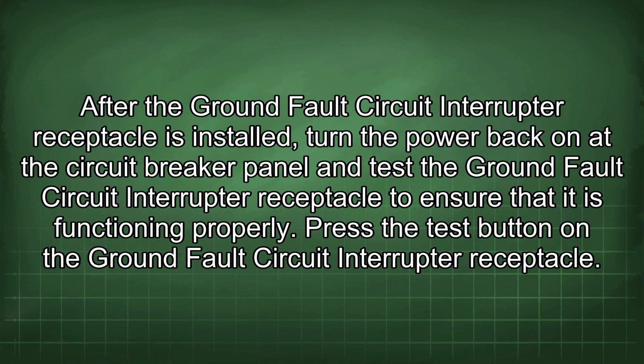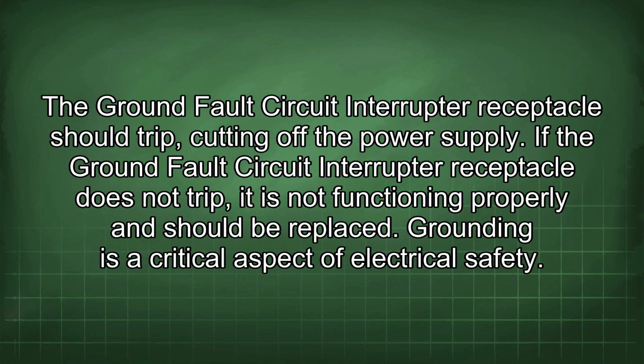Press the test button on the ground fault circuit interrupter receptacle. The receptacle should trip, cutting off the power supply. If it does not trip, it is not functioning properly and should be replaced.